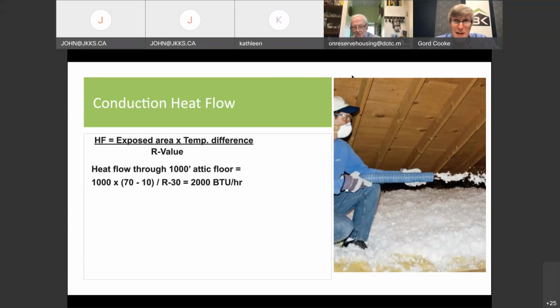But you would plug in what's called the design day temperature, not the coldest day ever, but what statistically represents the 50 coldest hours of the year. You'd divide that by R30, in this case, if we had R30 insulation in the attic. As you can see, that's pretty simple, straightforward math.